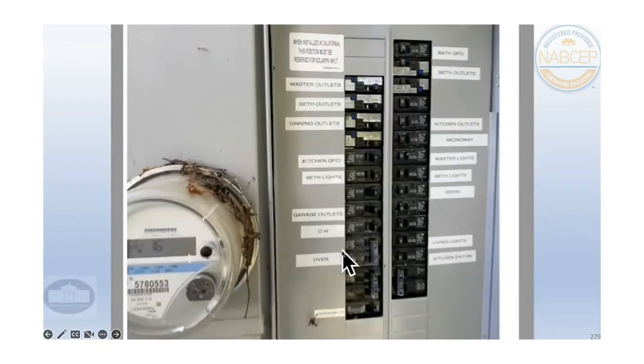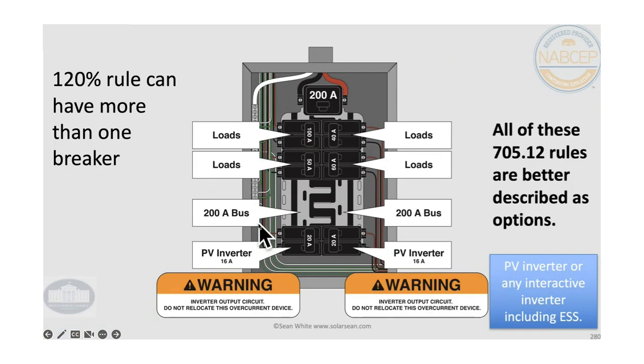It's interesting that in California, for new construction, they require you to leave an open space at the opposite end of the main breaker. So here it says, when installed in California, this must be reserved for solar PV input. And so the main breaker would have been at the bottom of this bus bar. So that's how that works.